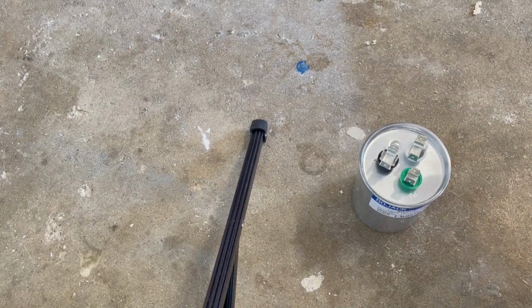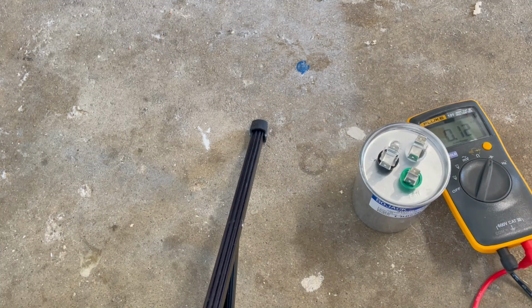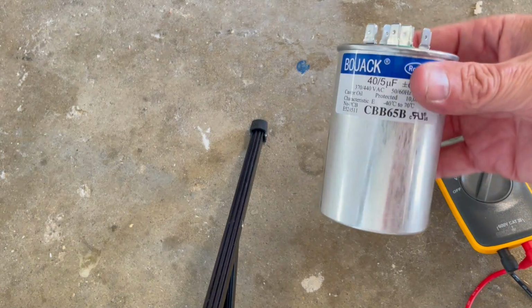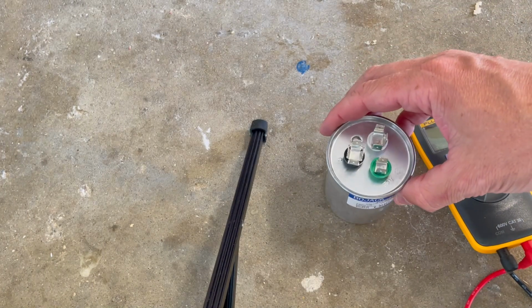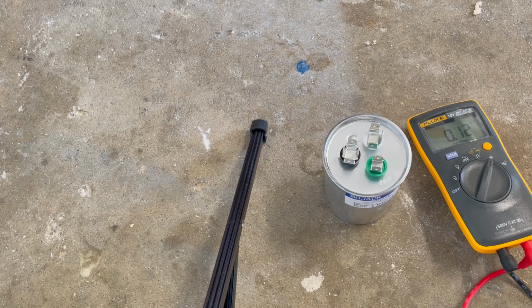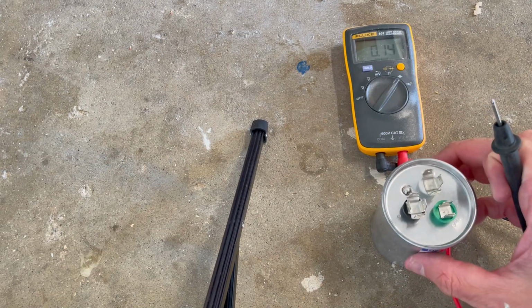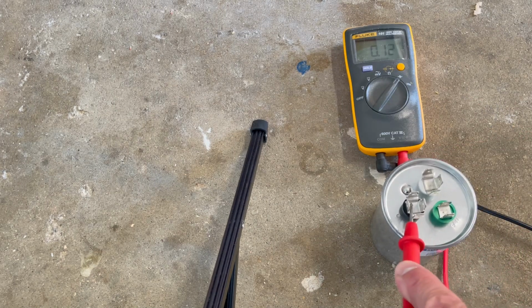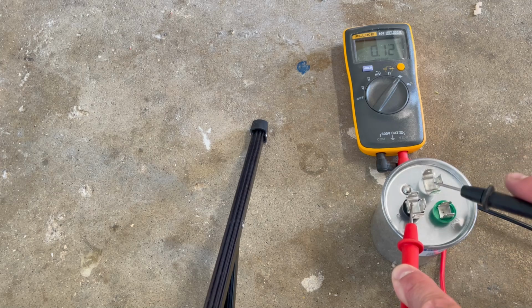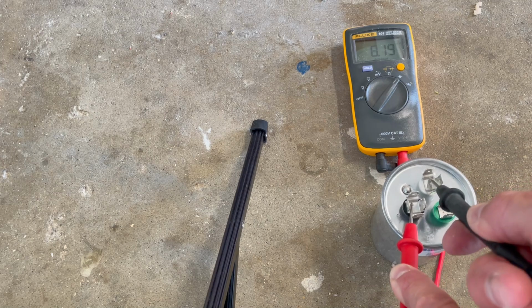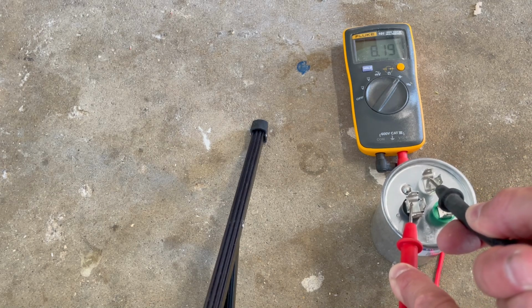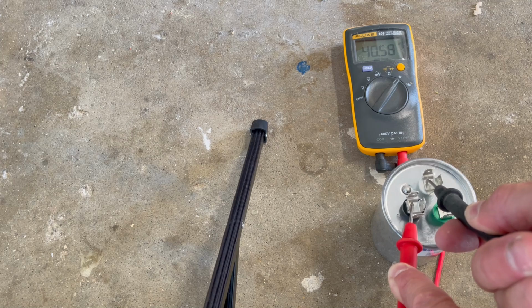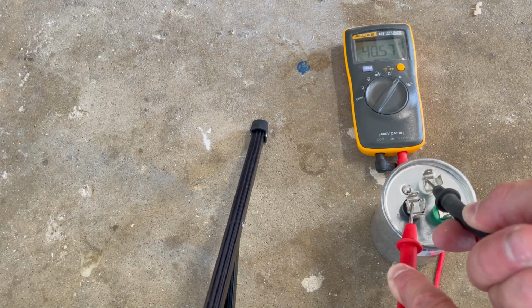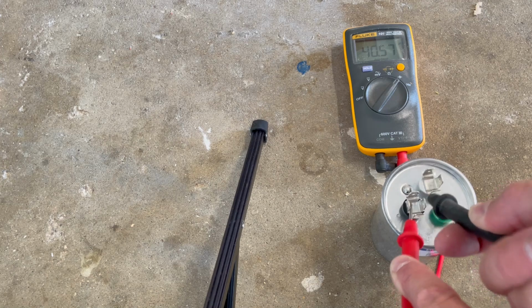So what I'm going to do is a quick check on our new capacitor and confirm they're within tolerances needed. I'll put one probe onto our common and one probe onto the hermetic, and we should be seeing around 40 microfarads — we're at 40.5. So we're well within the plus or minus 6% on the label, and that's perfect.